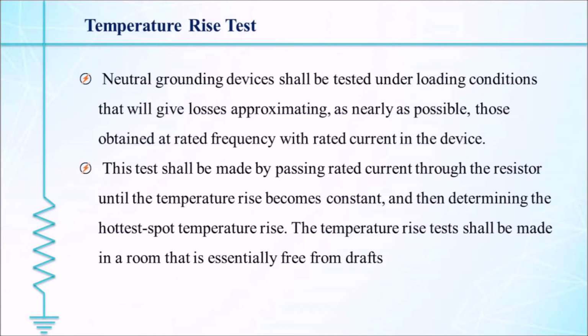Temperature rise test. In this test, a rated current is passed through the NGR and the temperature is recorded. If at the time of the test the temperature exceeds the limit, then the needed changes are made in the NGR panel and the temperature is maintained according to IEEE standards.